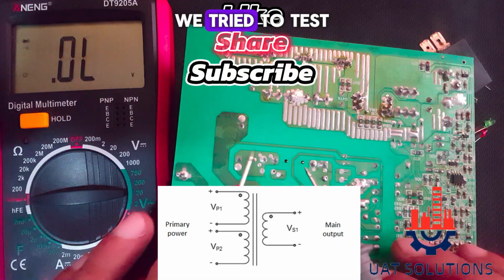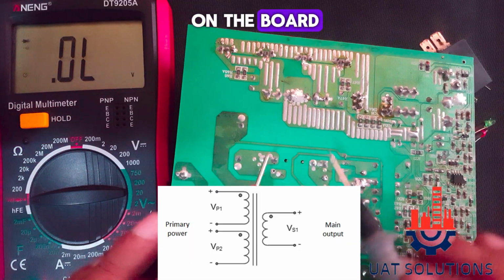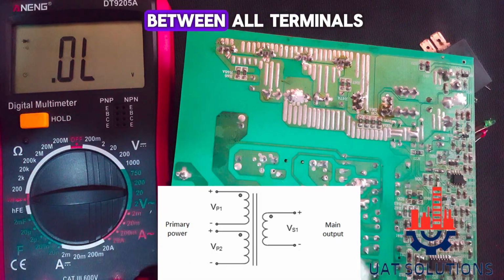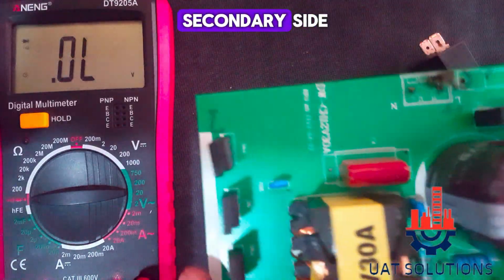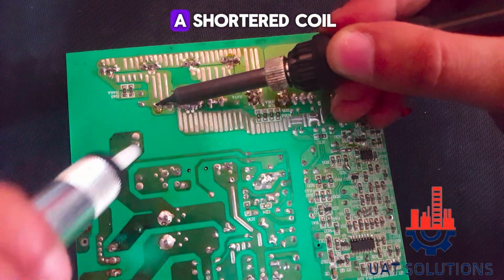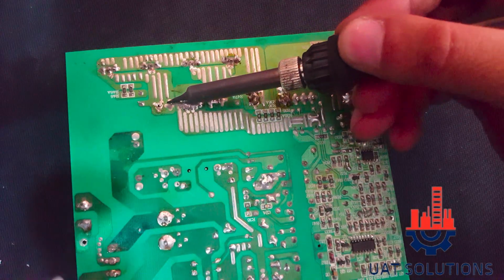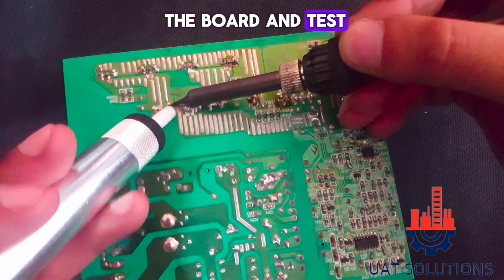As seen, we tried to test it while it's installed on the board and it's showing continuity between all terminals of the primary and secondary side, which indicated it has a shorted coil. Let's remove it from the board and test.